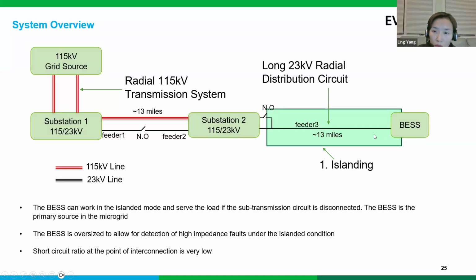So when we propose these projects, the primary use case of the battery is islanding. Because of the configuration of the circuits, if there is any distribution fault along this feeder 3, there is no other backup supply in the area. So the primary use case of this battery is to serve as the supply source for the island in the event of a distribution fault. And the other use case is, on a blue sky day, the battery will provide voltage support.